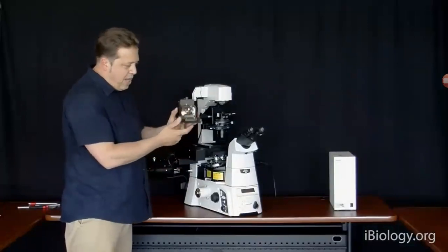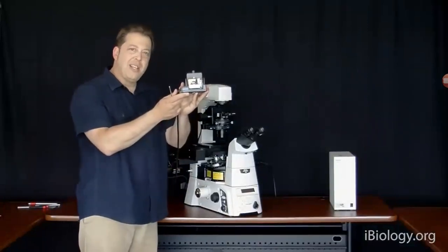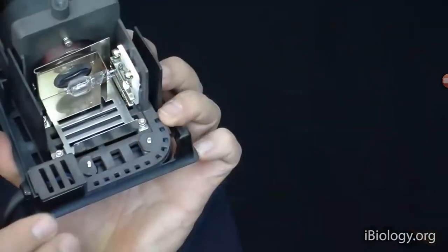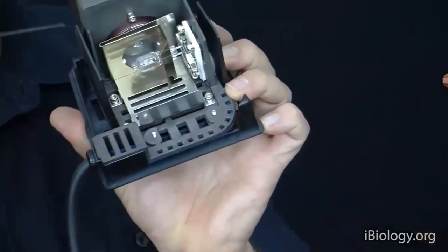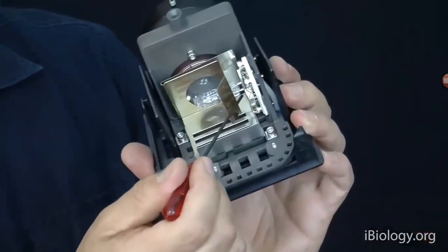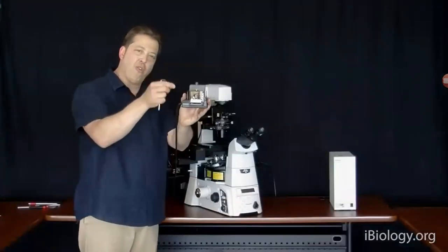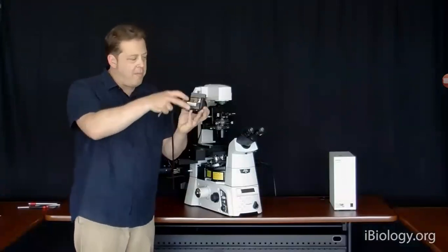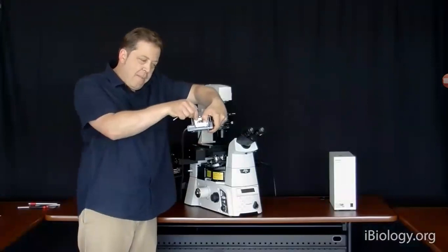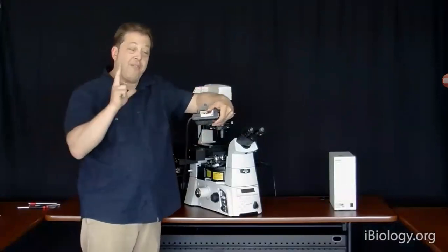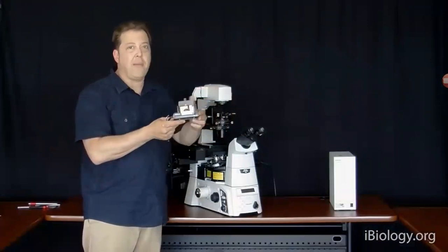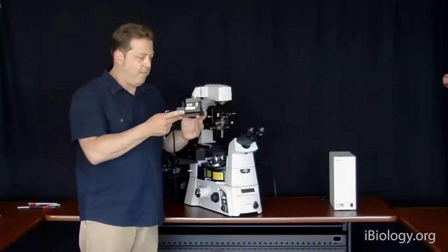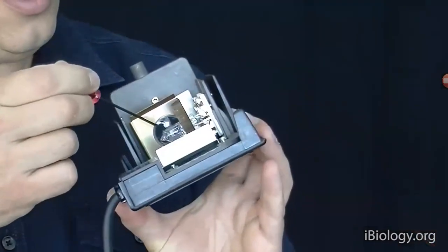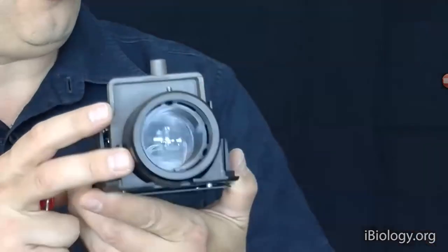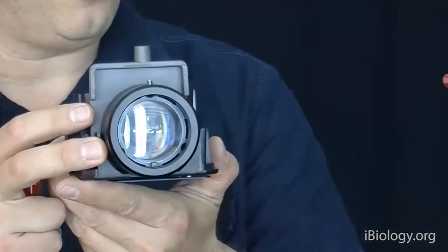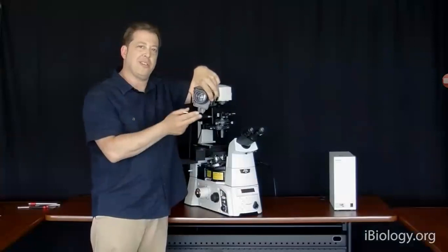And then below that cover, we have this component here. You can see that this component has the halogen bulb held by two metal clips and powered. When you install this bulb in the microscope, you want to hold it in the plastic bag it comes in, rip off the bottom of the bag, and then hold down the two clips and put the bulb in, and then pull the bag off. You never want to get the oil on your fingers on that bulb. That could cause the bulb to fail. Behind the bulb, you see the collector lens that I spoke about before, which is magnifying the image of that filament. Again, that is your first aperture plane in the microscope in the transmitted light system.